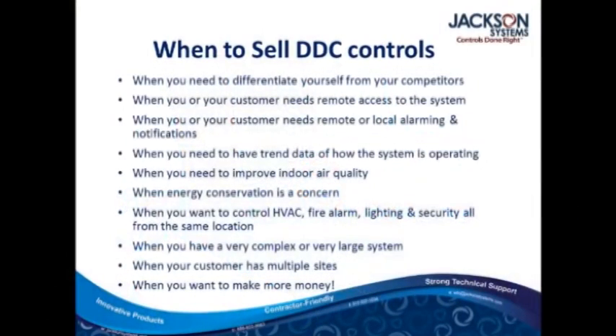Whenever your customer needs remote alarming, we'll pick on the schools a little bit. If you close your school down for Christmas break, coldest time of the year, if you don't have something to alarm if the boilers go down or a pump goes down or classrooms are below 50 degrees or whatever you want to set your alarms up for, if you didn't have remote alarming, you'd have to have somebody in that school at least go by and check it once a day during Christmas break or something along those lines.